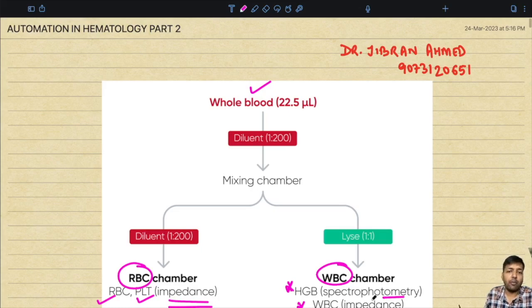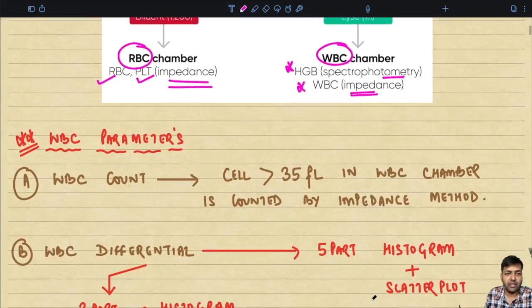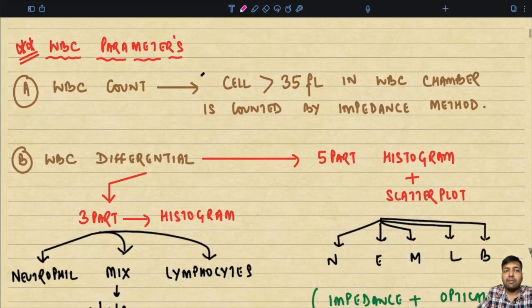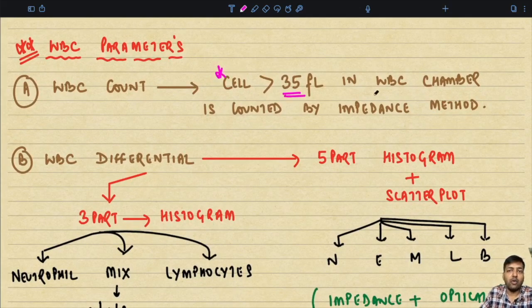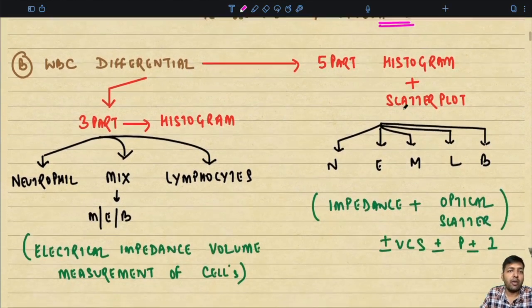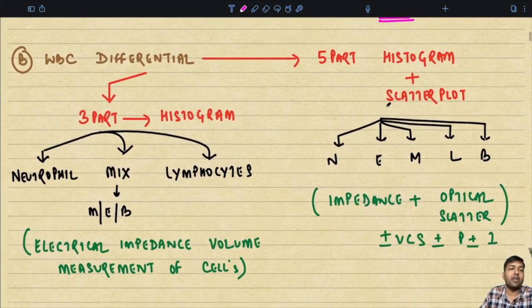Let us continue today's topic of discussion. Looking at the WBC parameters: any cell measuring more than 35 femtolitre in the WBC chamber is counted by the impedance method. The second important parameter is the WBC differential count.